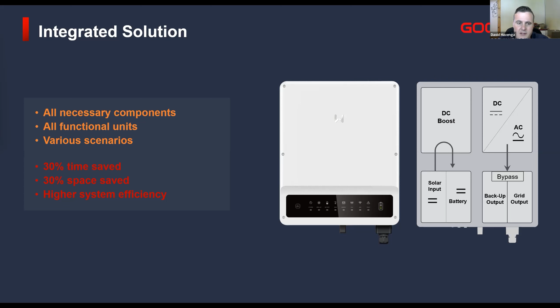So overall efficiency from charging your batteries to running your loads, you get better efficiency out of your systems, especially when one looks at the high voltage with the EHP and so forth. You're going to get much better DC to AC conversion efficiencies. That's normally where a lot of other devices might give you a lot less efficiency. So even though you have a 10 kilowatt hour battery bank with only 70 or 80% efficiency, and with only a limited amount you can take out of your battery, you're going to get a lot less actual kilowatt hours in AC out of your battery, whereas with the higher efficiencies of high voltage and so forth, you're definitely going to get a lot more out of your batteries and a lot better value in the long run.